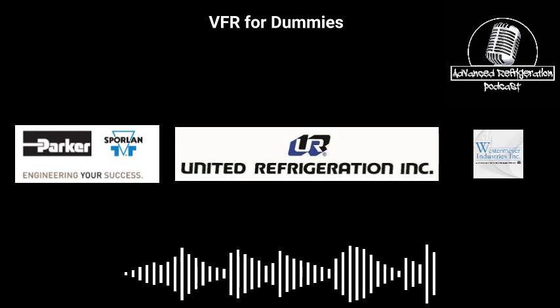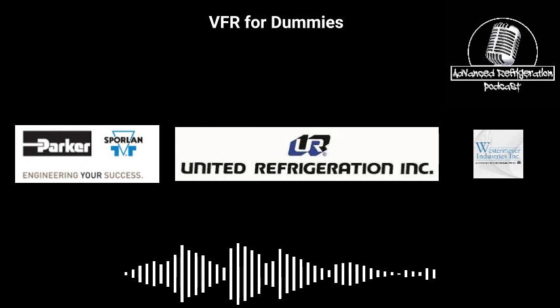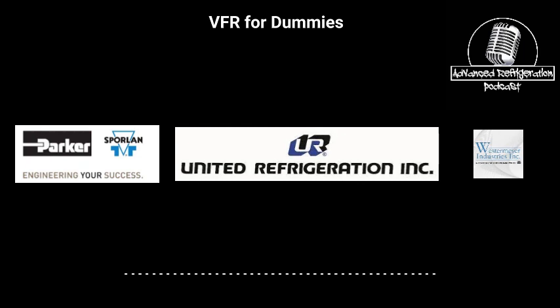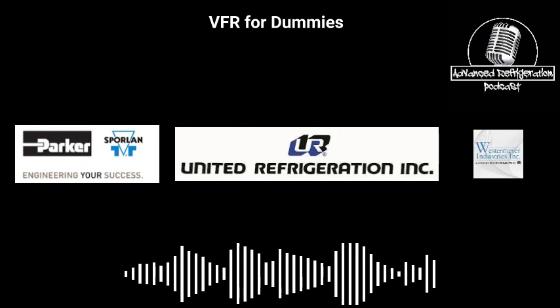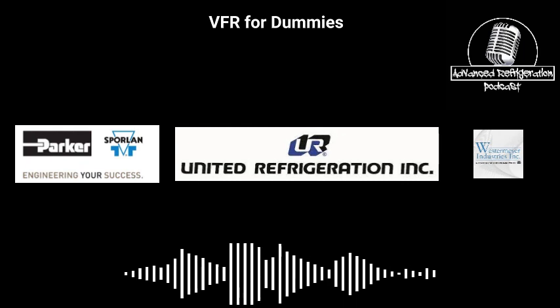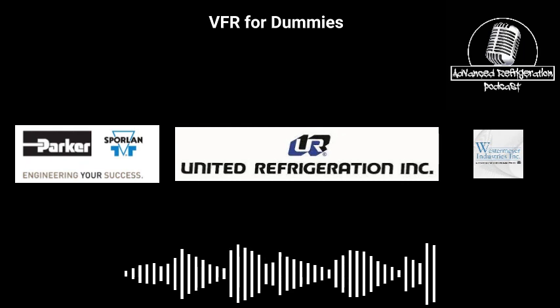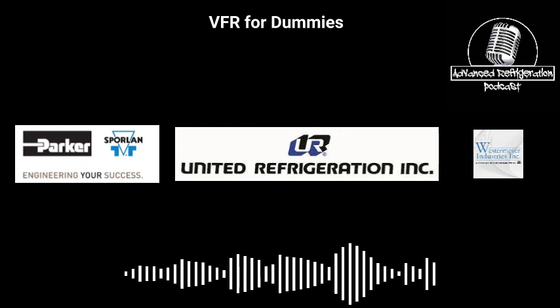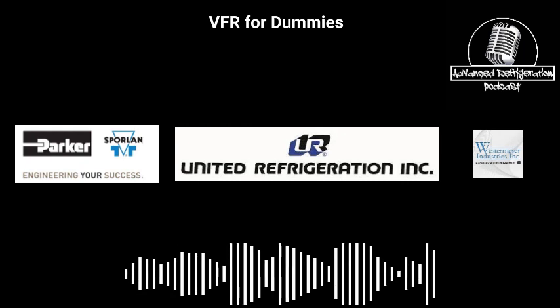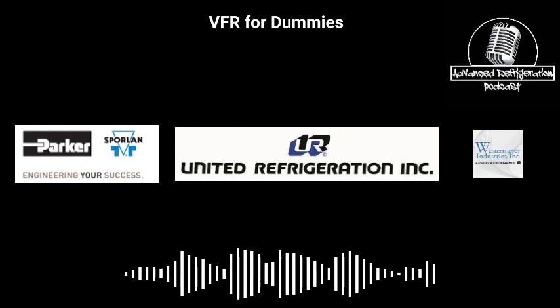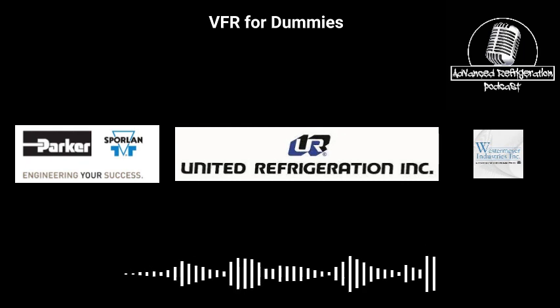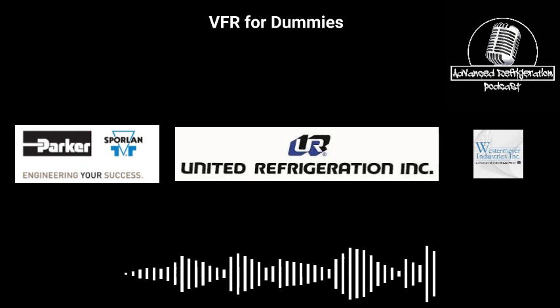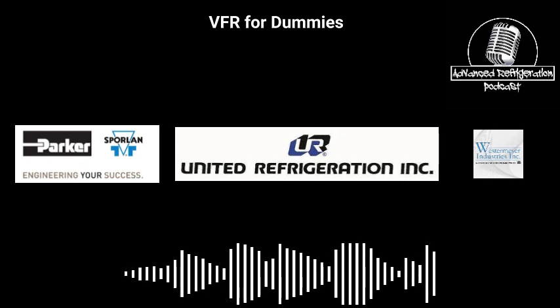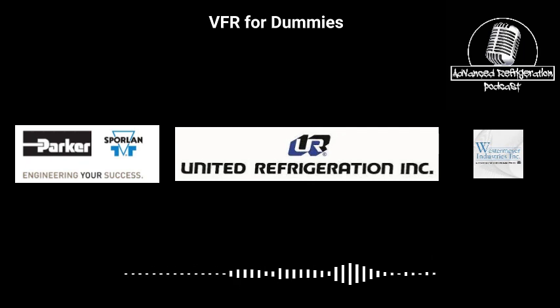So let me just make sure I understand that. So when they're calling for heat, but utilizing the liquid for the heat, that's when you say they flood out the most. So dual operation. Say we have the smallest multi-port, a 4-port box. If ports A and B have their control wires switched and they're calling for opposite modes of each other, the fan coil that's calling for heat will never heat. But because it never heats, that expansion valve keeps opening, and all it's doing is just letting liquid flood right through. Okay.